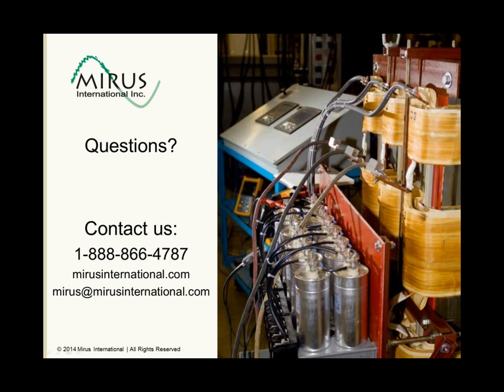One question that's come up is whether we've had any problems in applications involving generators and our filters. Provided the total Lineator load connected to the generator does not exceed the generator's full load rating, we have never had a problem with the generator. If the connected load is much larger than the generator, in some cases that will still work, but if it's excessively larger, then you might have problems.